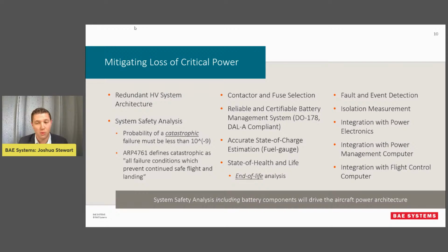Fault and event detection, being able to detect ground faults and measure isolation, is very important. If you end up with a low impedance to ground, you can have catastrophic failures in your battery system. One of the worst is a double ground fault, where you have two low impedance paths to ground, and if there isn't proper fusing between those connections, it turns into a very high current short, producing a lot of heat. That's not good.